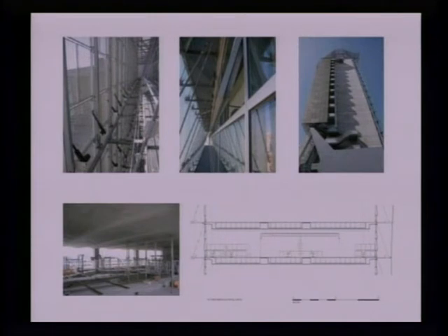So this building has a narrow floor plate. This is primarily to allow cross-ventilation. It has active thermal mass, which just means that the concrete is exposed to the room air. And at night, they use a night flush ventilative cooling method to open these clerestory windows automatically to allow airflow to move. The Bay Area climate is quite cool at night, and so they move that air across the ceiling, cooling that slab down in the evening, and then flushing the heat out and having that slab pre-cooled during the day to moderate the indoor temperatures without air conditioning.